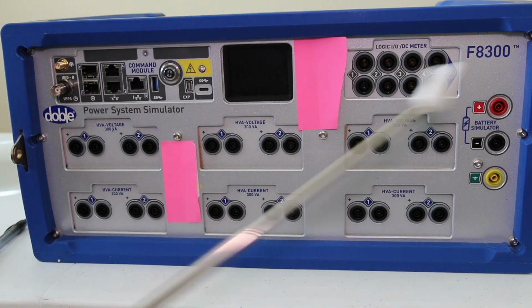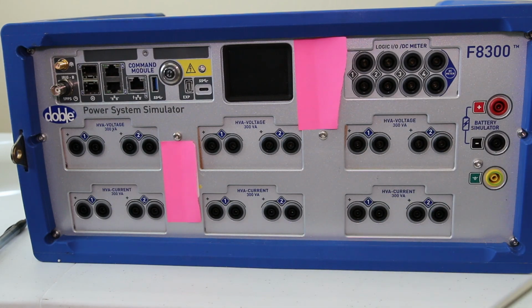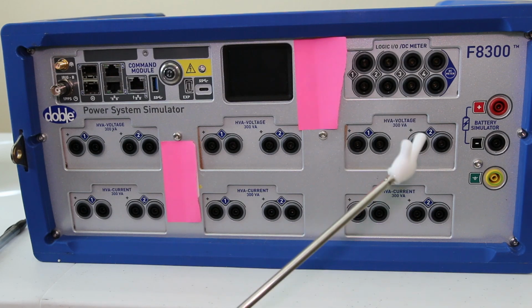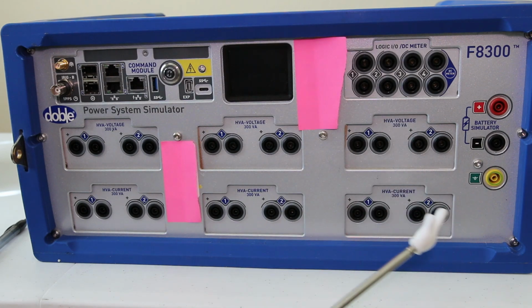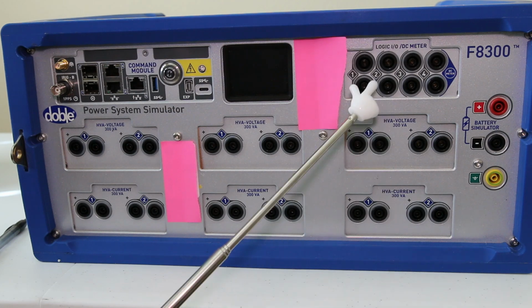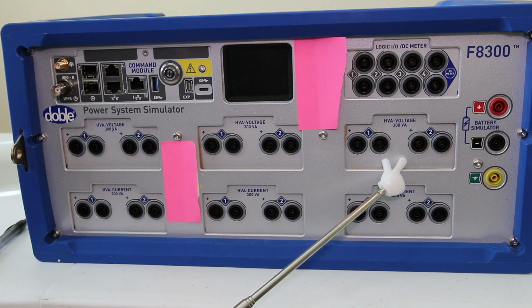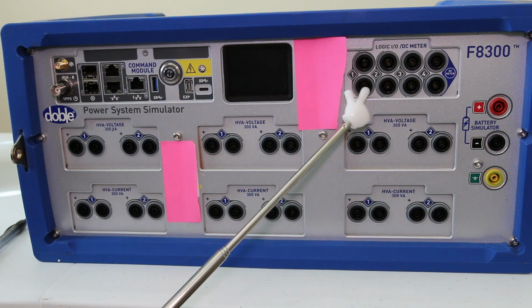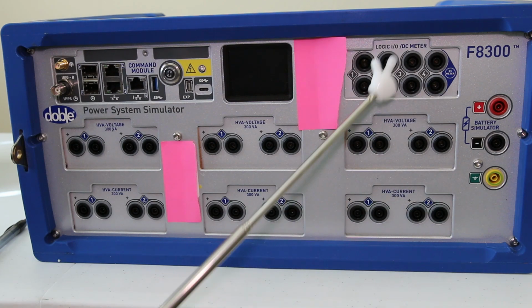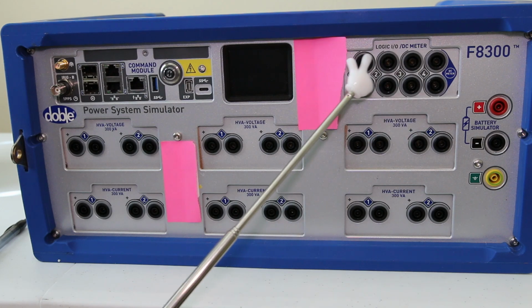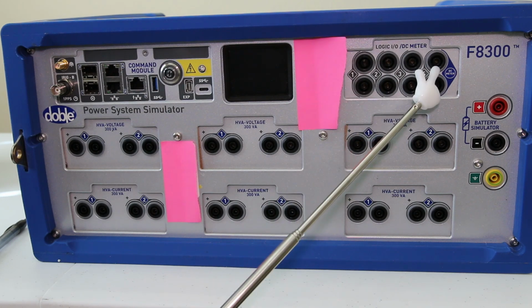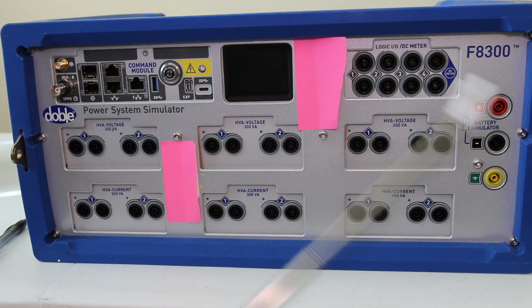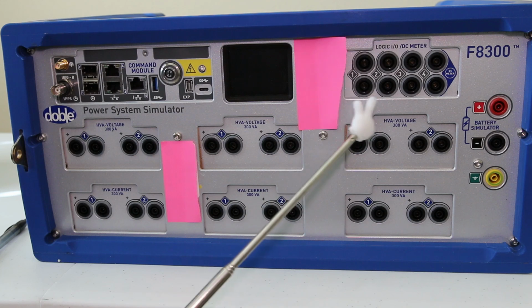I think this setup makes the most sense for just generic relay testing. You should be able to do basically everything you need to do with it. If I had to change anything, or wanted one extra spare module, I might get another one of these logic IO modules to keep around—that might get swapped out with this at some point for some applications. If you look at the top of a 6150, it's got an absolute crap ton of IO, and this one only has 4. Now these are 4 convertible ones, so this could be 4 digital inputs or 4 digital outputs, but sometimes that's just not enough for what we're doing, so I might consider buying a spare one of these to keep in the case.